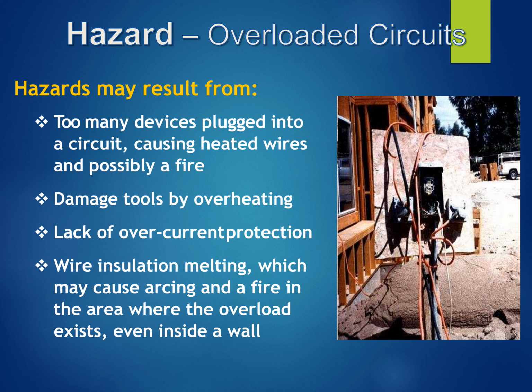As I mentioned before, an undersized wire, not sized correctly, when it draws power from the power supply, the normal sign that the wire is undersized is that it gets very hot. If you feel the wire, it will be very hot. Those are the signs of overloading, meaning if you frequently and prolong the use of that equipment with an undersized wire, eventually it will cause a fire, and of course we don't want that to happen.